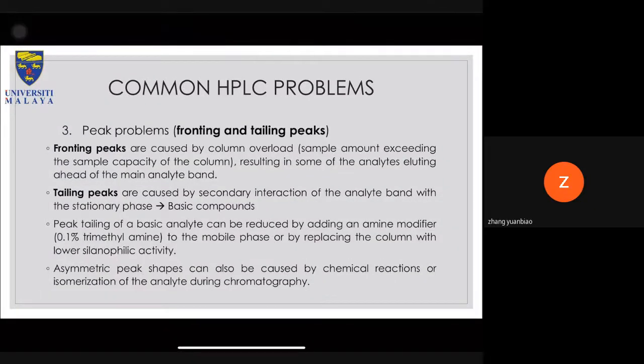Okay. Fronting and tailing peaks. A fronting peak means the tailing is at the very beginning of the peak. Tailing means it goes up and then tails out once it's eluting out. It's normally caused by column overloading, where the sample amount exceeds the sample capacity of the column, resulting in some of the analyte eluting ahead of the main analyte band. If you do see something like this happen, to solve it, you just inject less sample.